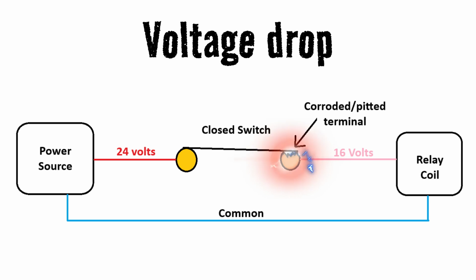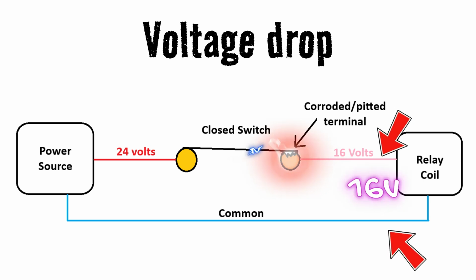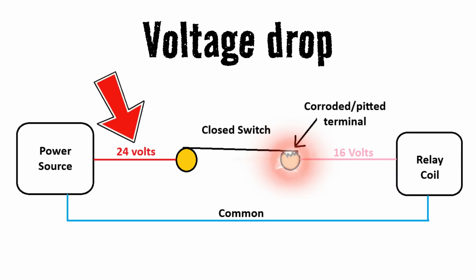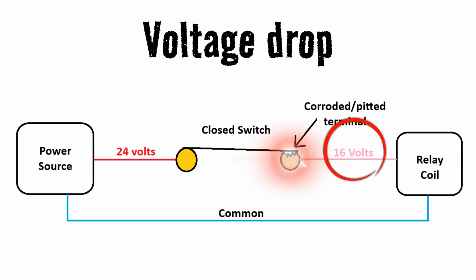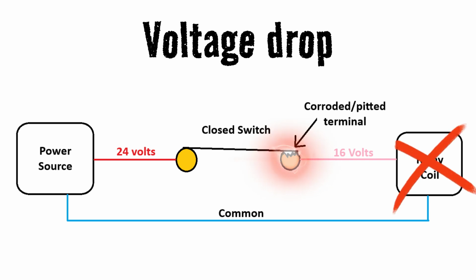And so what we end up with is a measurement on our multimeter that shows a drop in voltage prior to our relay coil in this example. So we can see we have 24 volts coming into a closed switch, but we only have 16 volts coming out. And that 16 volts is not sufficient to actually activate the relay coil. So this is something you're going to run into a lot out there in the field.